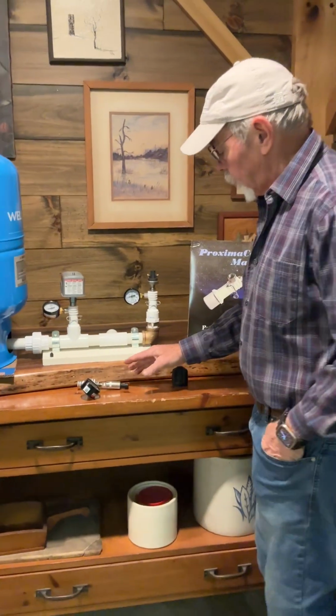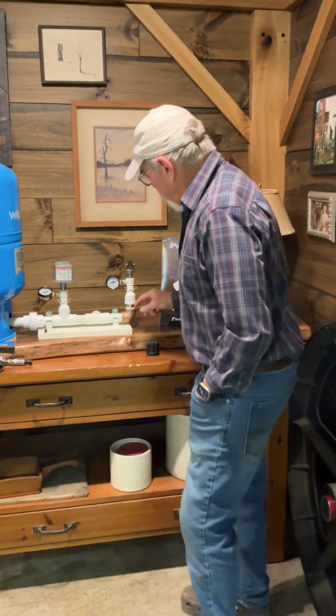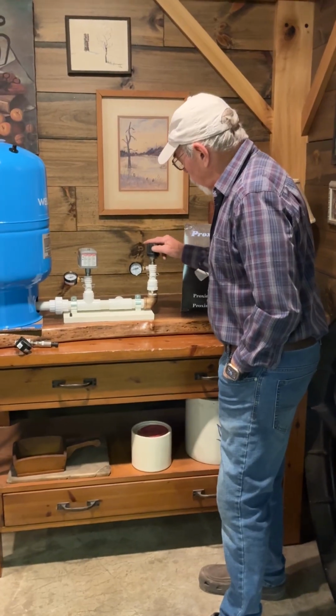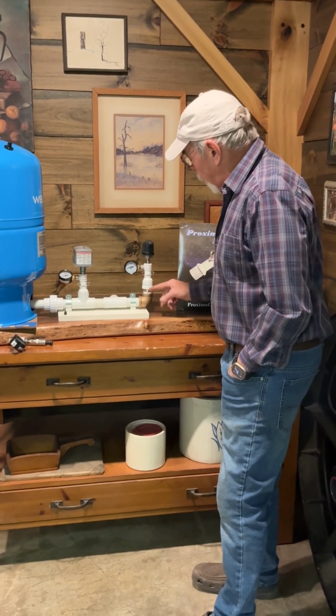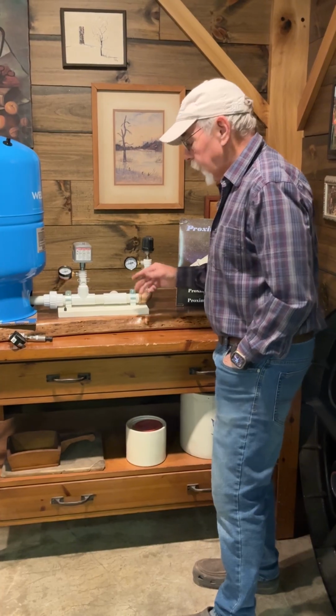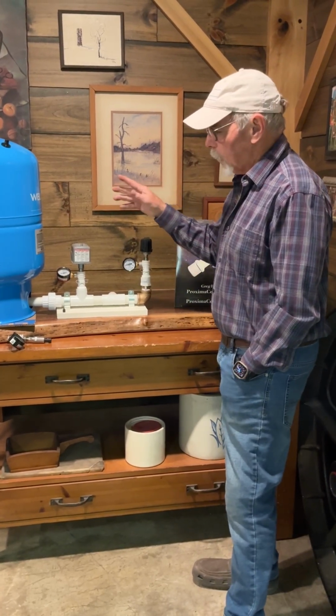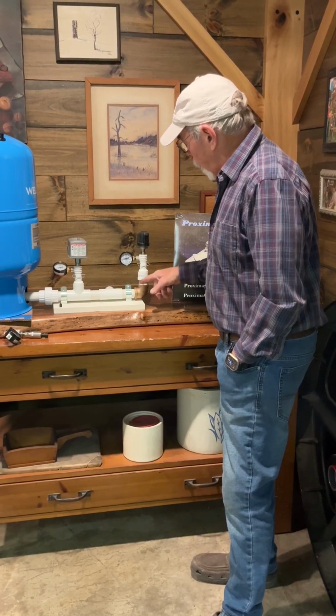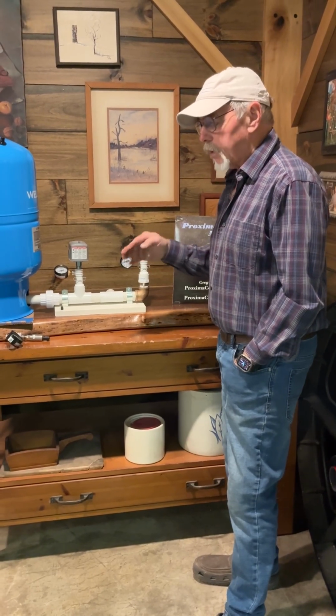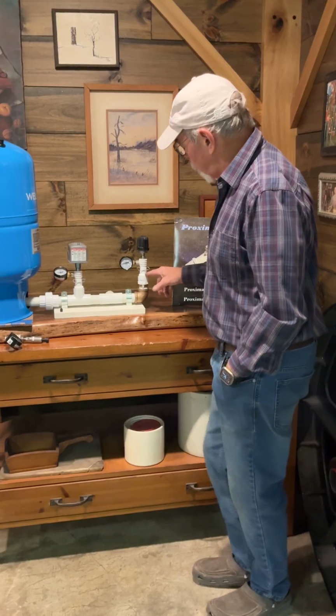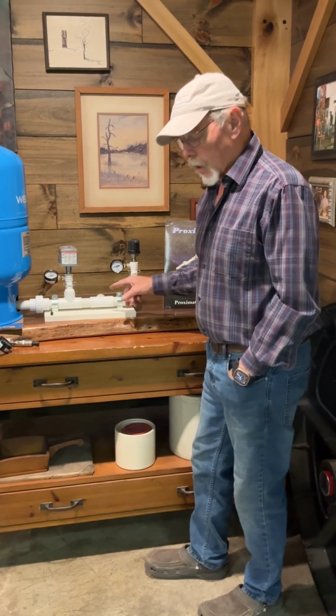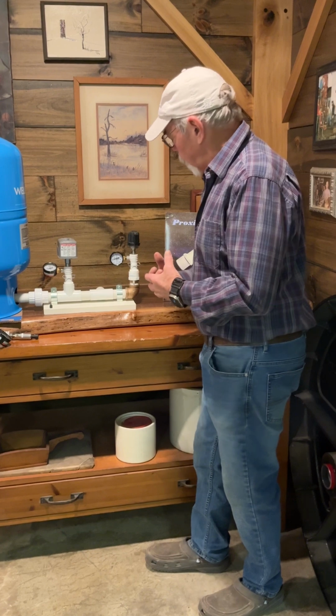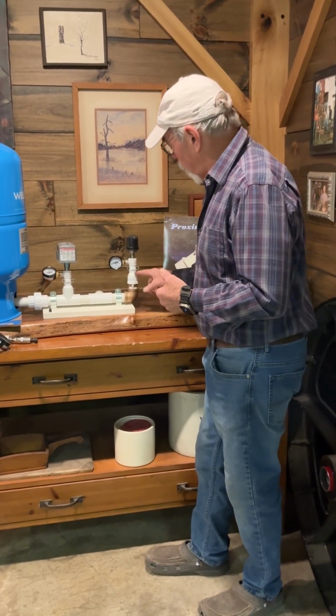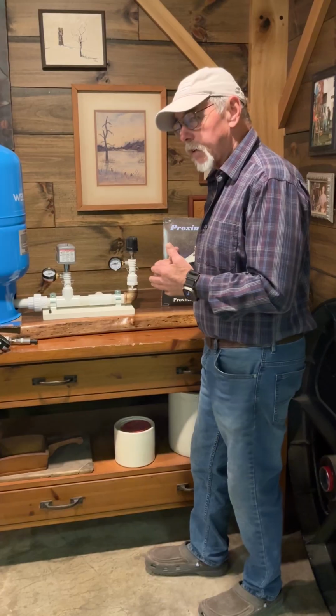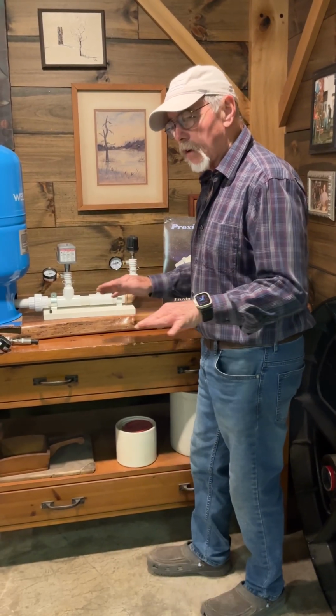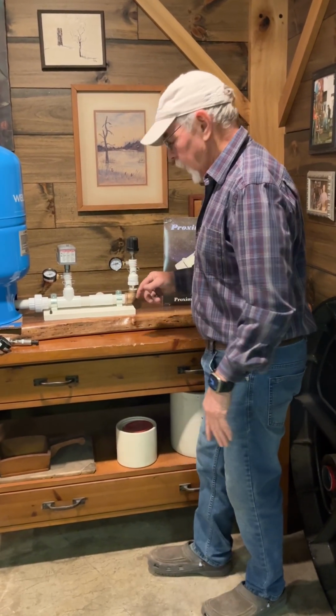About transducers and pressure sensors: a lot of times when you have one in a tank T, on a manifold, on a wall, however it may be, you can get some cross fluctuation and the drive does some of this stuff. These seem to help combat some of that, because there's that 3/8 hole I showed you at the bottom, then there's a water chamber up in there, and then it's going through a passage of the check valve. It kind of helps even out some of the up and down fluctuations, so they're good for that too.